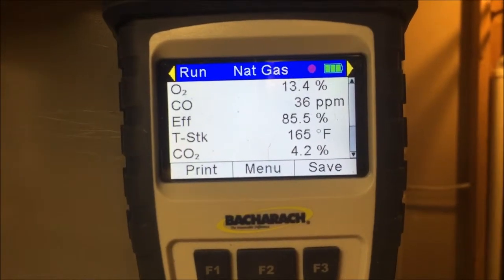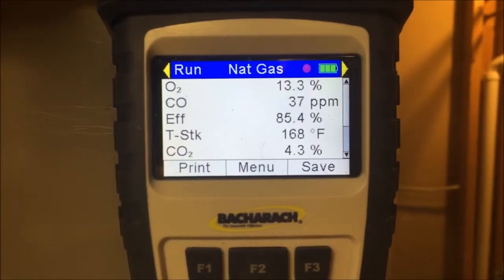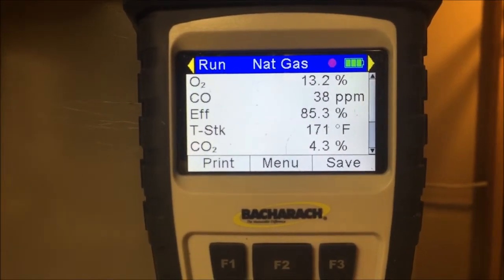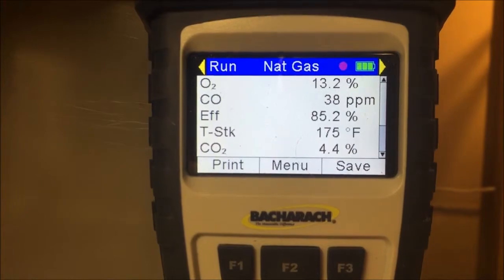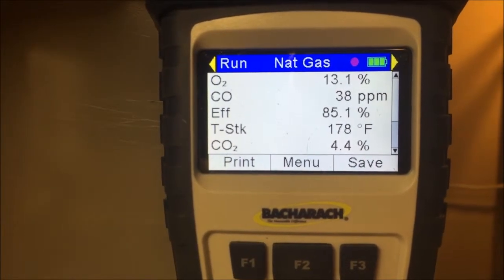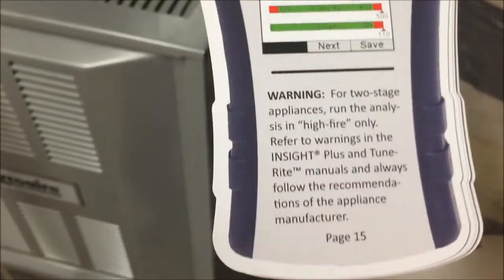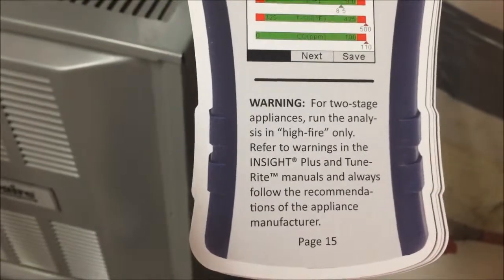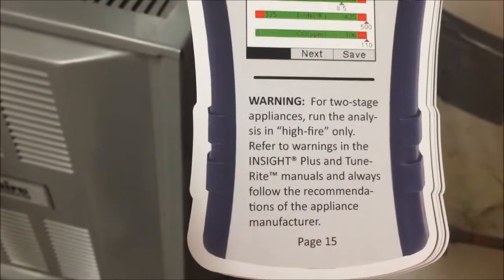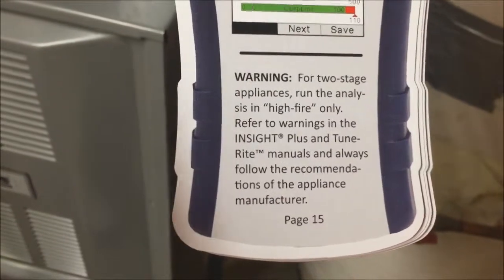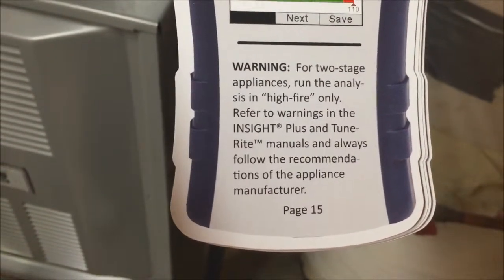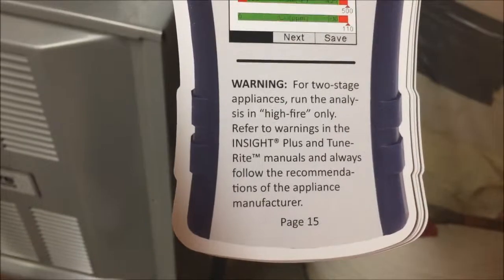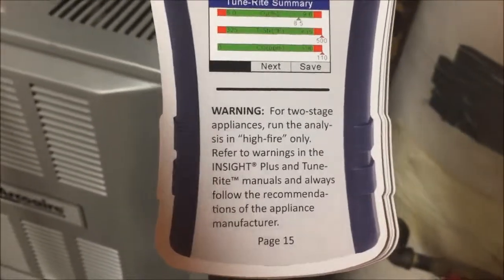In the reference guide of the Bacharach, there is the notation. I'll show you this right now. For two-stage appliances, run the analysis on high fire only. Refer to warnings in the Insight Plus and Tune-Rite manuals, and always follow the recommendations of the appliance manufacturer. High fire. Don't run these things. Don't try to get these things into spec on low fire.